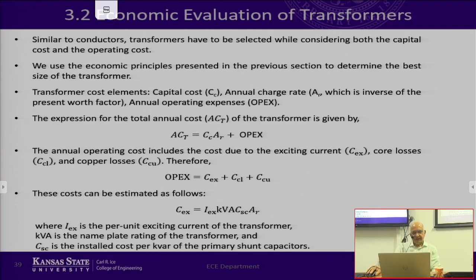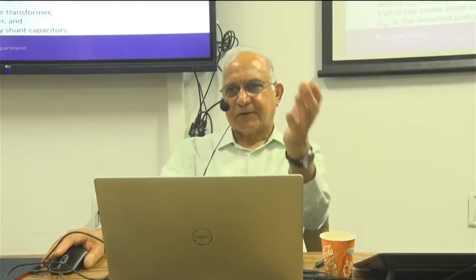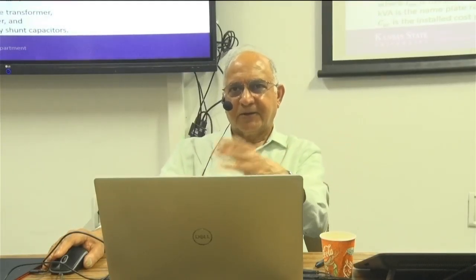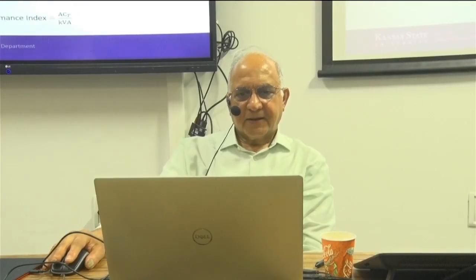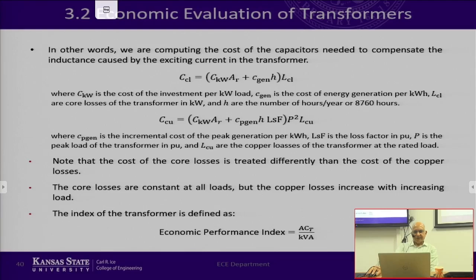The way we are estimating this cost is by saying that the excitation is inductive, and how do you cancel that with capacitors? So if you were to cancel the inductive part with capacitors, what would it cost you to do that? The cost is actually calculated based on that factor. You're not actually putting in capacitors, but you are compensating by saying this is the cost associated with that. As far as the cost of capacitors needed to compensate the inductance caused by the exciting current in the transformer, it is given by...